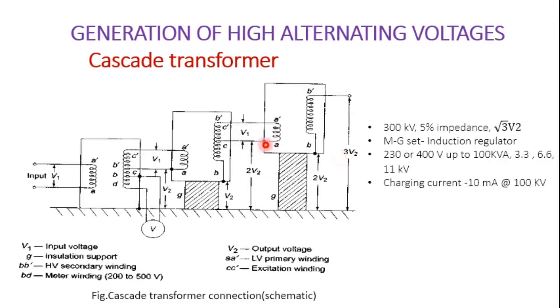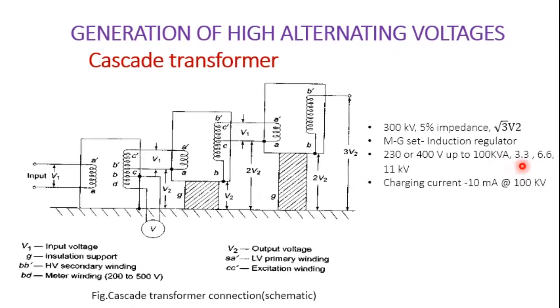Similarly, the input given to the third transformer results in a rise in voltage of 3V2 across the third transformer. Generally we will have 2 to 4 stages, but very often 3 stages are adopted to facilitate three-phase operation, giving about 3 times the V2 value. The input from the motor generator set is around 230 or 400 volts, single phase to three phase, and the transformer rating is around 100 kVA, resulting in secondary voltages of 3.3, 6.6, or sometimes 11 kV.